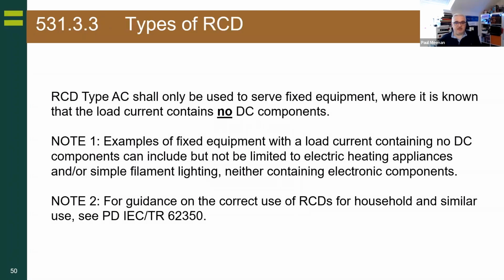So in that regulation, it also has a fantastic argument, which is RCDs Type AC shall only be used to serve fixed equipment where it is known the load current contains no DC.